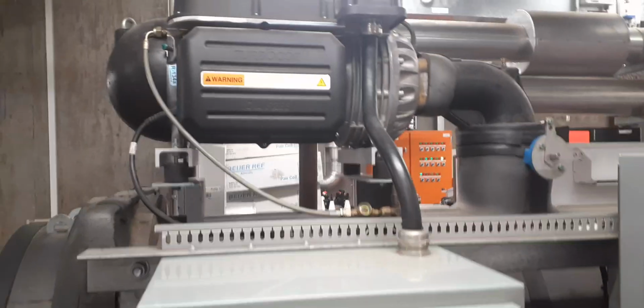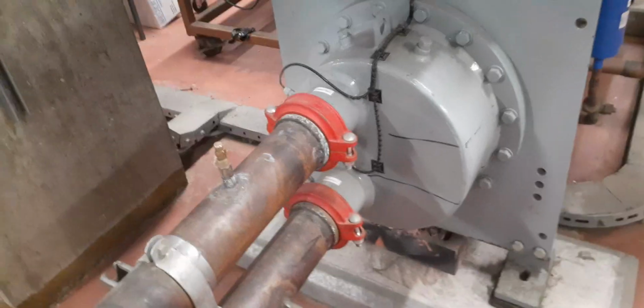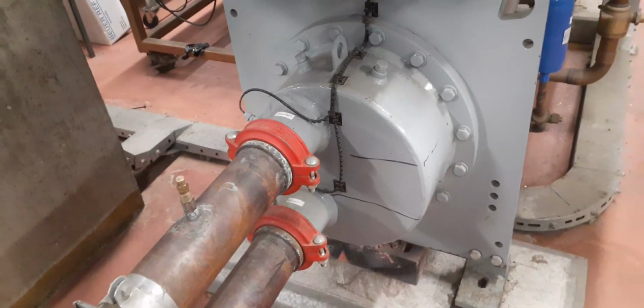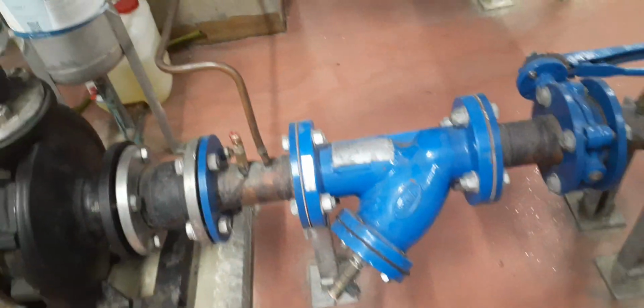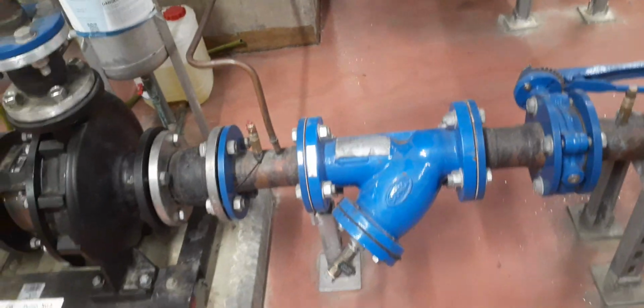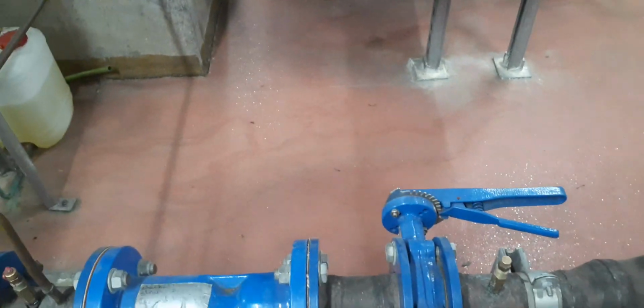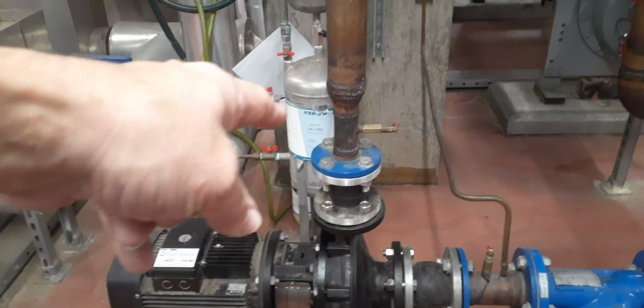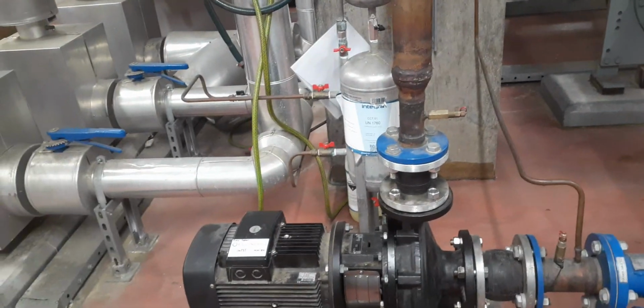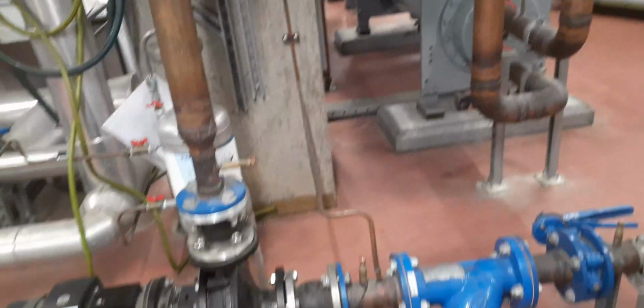The major component of this, of course, is the centrifugal compressor. That there is called the shell and tube condenser. The standard is the temperature of the water coming from the cooling tower. So let's just have a quick look at this. That's coming from the tower, and the other one's returning, coming down into the suction via the strainer. So if you need to clean your water, you need to check that regularly for catching rocks and that sort of thing. So you've got a butterfly valve there. You shut that off. You should also have a check valve here, a one-way non-return valve, and perhaps you should also have another butterfly valve so that you don't get water everywhere.